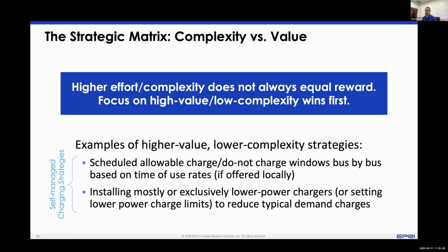If that's an offering for your tariff, that would make a strong value case, as well as just right-sizing the charger. By installing a lower power charger for most of your buses, you don't have to worry as much about demand charges, since you'd be capped at the charger's limit even if everything charges simultaneously. With higher power chargers, you'd need to consider setting software limits or other measures to ensure that. So those are the two easy wins, and we'll get into grid services in a moment.